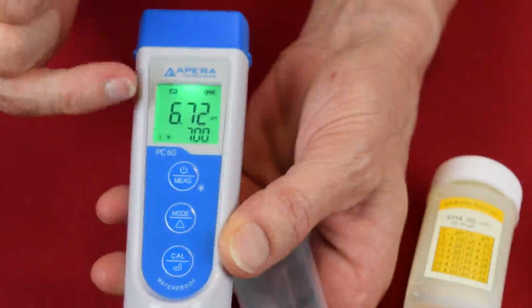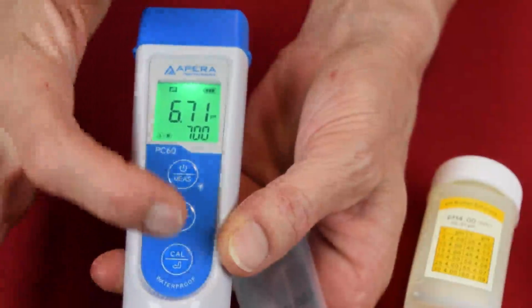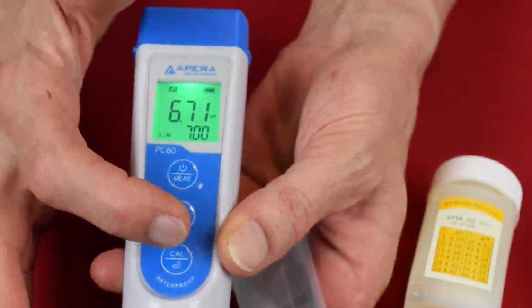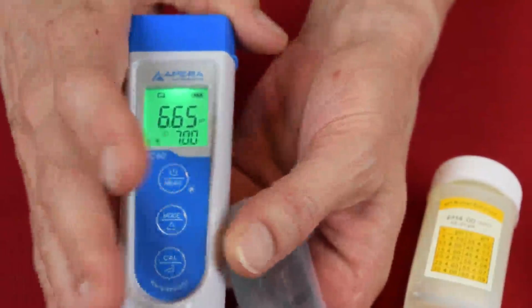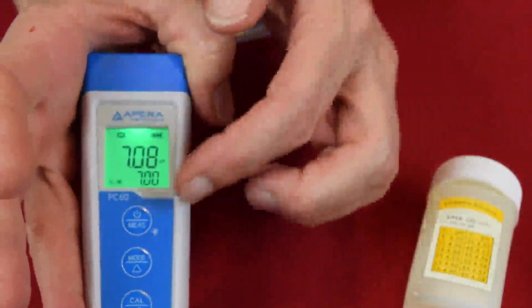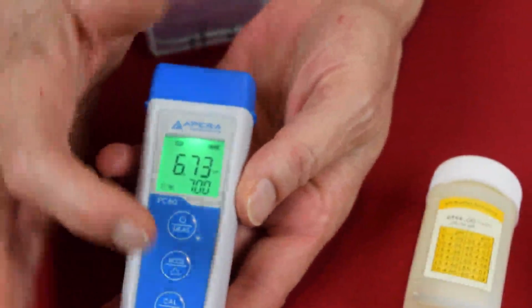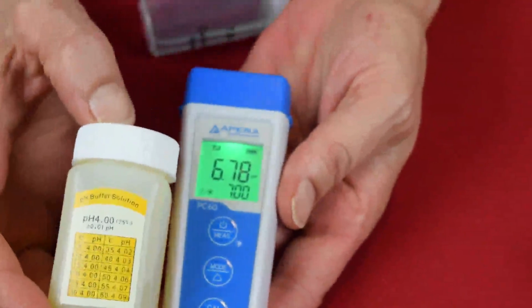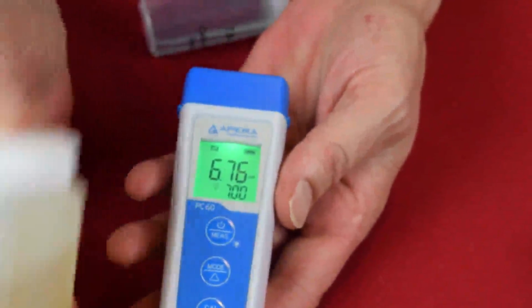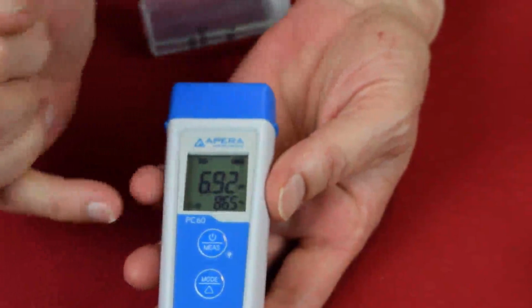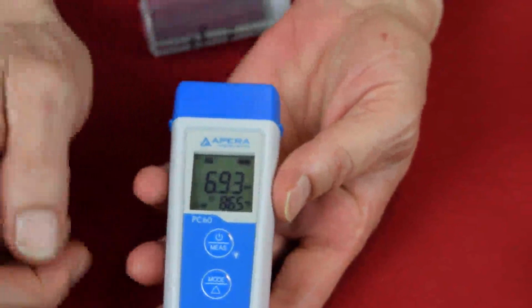Once you have that smiley face for a few seconds, then you press the CAL button again to set that calibration. It knows when you're putting it in the 7 pH solution. After you're done doing that, then you press the CAL button again and do the same thing with the 4 pH solution. So you can see that this thing has been calibrated.